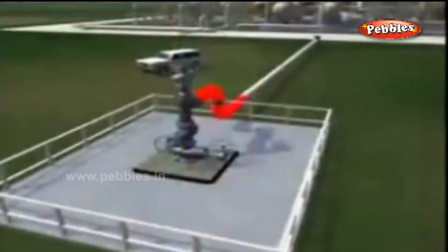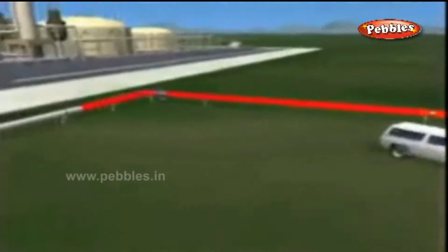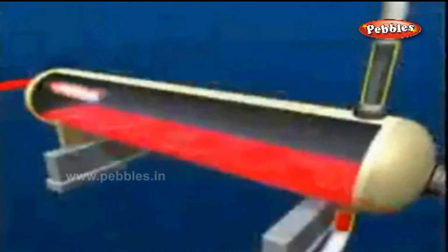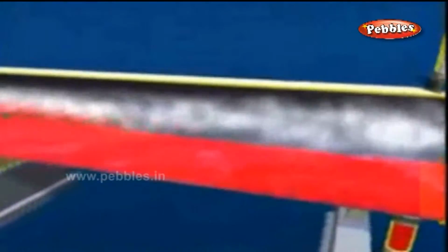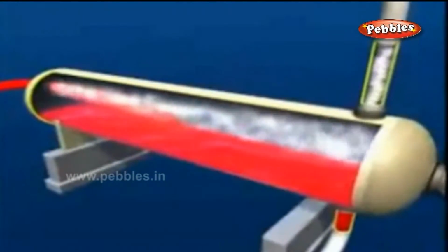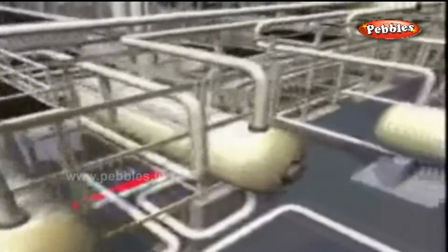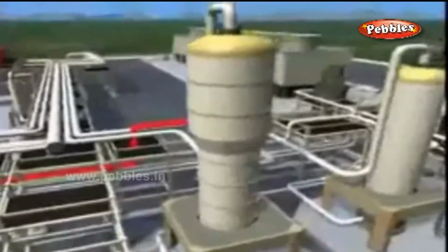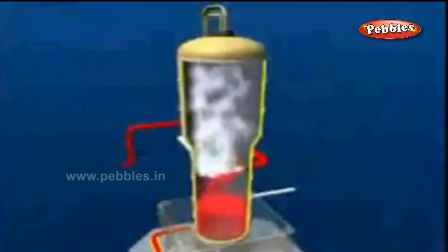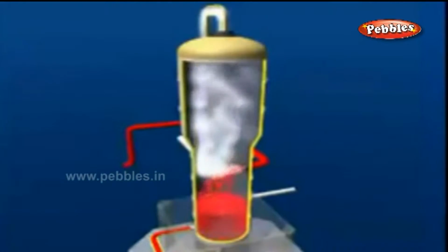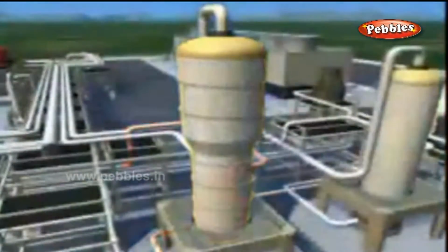At the surface, the superheated fluid and steam mixture flow through surface pipelines and into a wellhead separator. Inside the separator, the pressure of the superheated fluid is reduced. This causes a large amount of the superheated fluid to rapidly vaporize and flash into high-pressure steam. The geothermal fluid that is not flashed into steam in the wellhead separator flows to a second vessel called a standard pressure crystallizer, where an additional amount of standard pressure steam is produced.